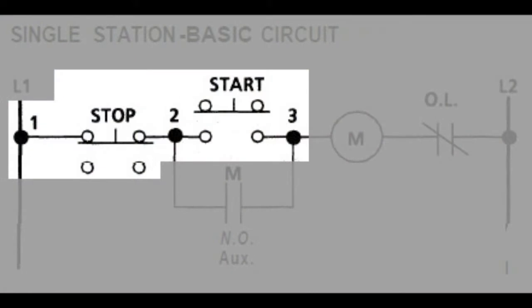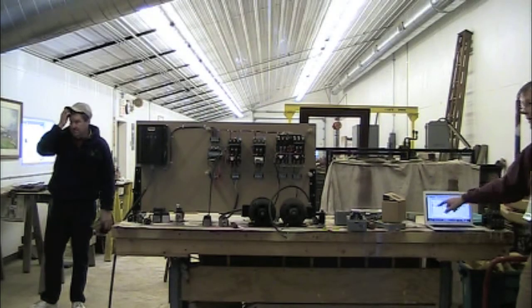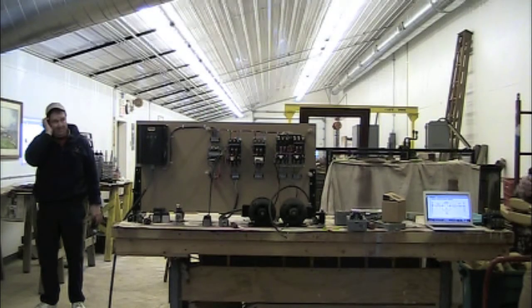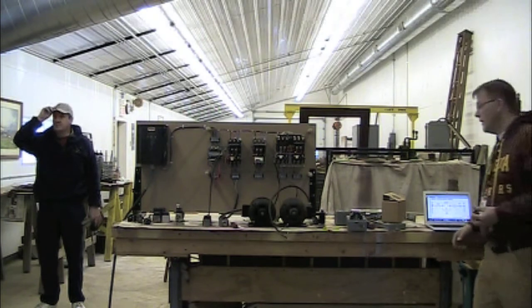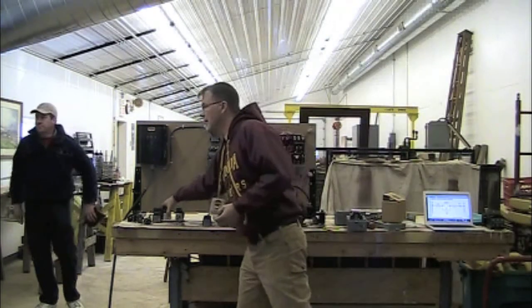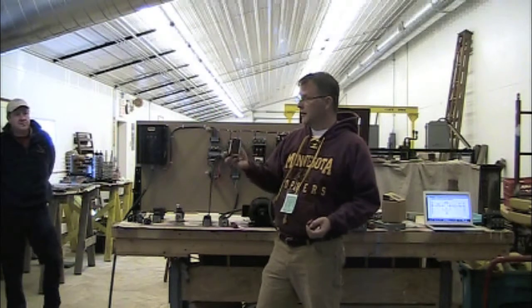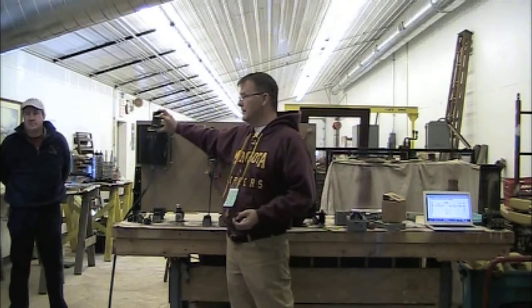In that scenario here, I was going to have this set up so I could project it or whatever. So this right here is the stop start station. But the nice thing about the setup of this, with the stop always in the beginning part of the circuit, so if you follow the convention, it's very easy to add more stop buttons because all they are is wired in series. You just add one in here, and it doesn't have to be a maintained one, it could just be a regular stop button. You can just have a button that you just want to hit, as long as it's normally closed.